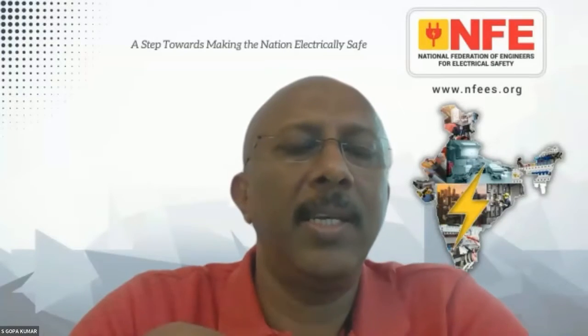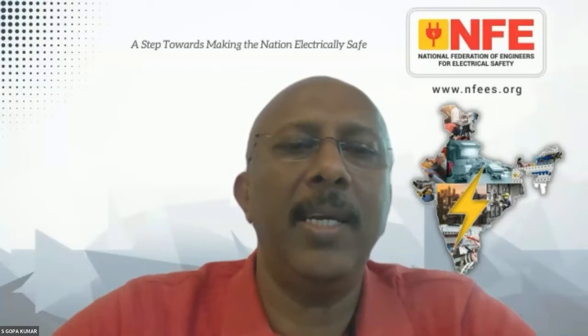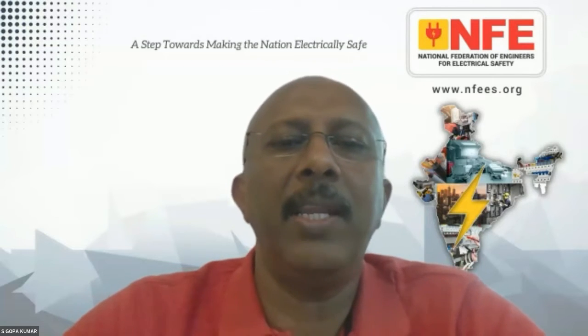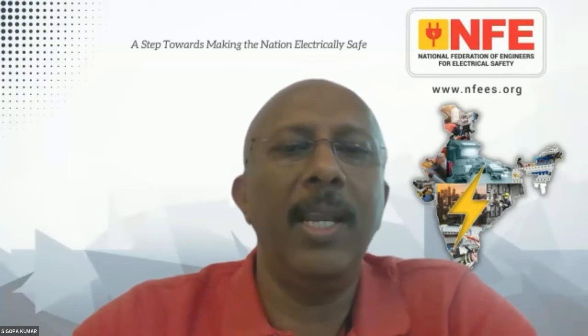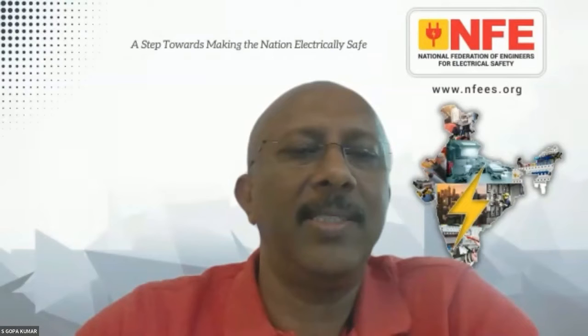And in respect of underground lines, in our regulation, I think number 70 or something, they have given what the clearance should be between telecom cable and power cable. The question is regulation 80, is it applicable from 11 kV onwards? Yes, the answer is very clear because the regulation says 11 kV and above. So this clearance is required for 11 kV and above. Yes, right. So 11 kV is included. Actually, for 33 kV, the distance is now 30 centimeters, and above 66 kV, the distance is 60 centimeters. That is mentioned in the regulation.